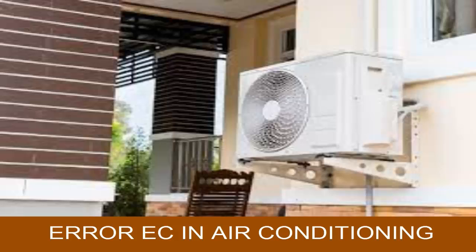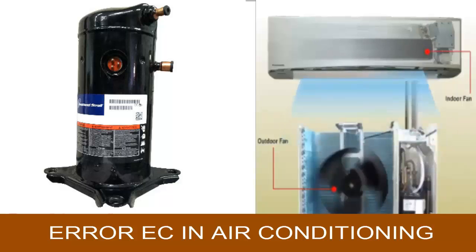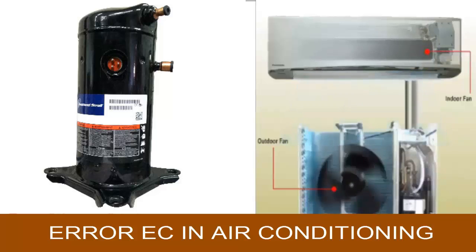If, after resetting, the external unit or condenser doesn't start, it indicates a communication problem or a voltage issue. Check the power supply to the external unit, cable connections, and possible cable damage. If the external unit starts, check if the compressor is running. If it's not, inspect the cables for damage or issues with the capacitor or the compressor itself.